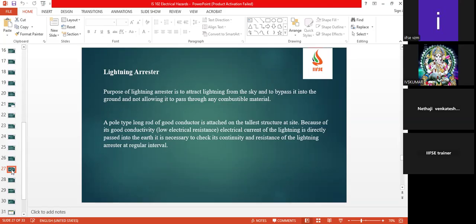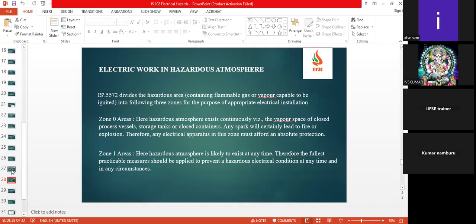It will have its own radius, so that within that radius it will protect the buildings from this energy discharge. Basically it is a very good conductor. They prefer aluminum and copper. Mostly they prefer copper strip as a good conductor. If you go for a lower cost side, aluminum will be used as a conductor for this lightning. Again, this lightning arrestor will be connected to a separate earth pit, and it is not going to be connected with any other earth pits, to avoid impact on the other equipments, etc.